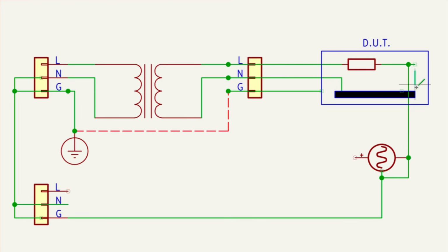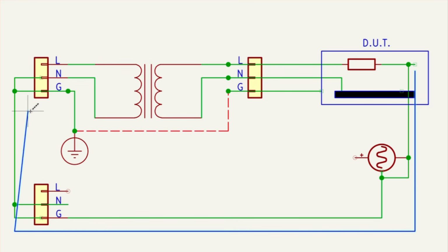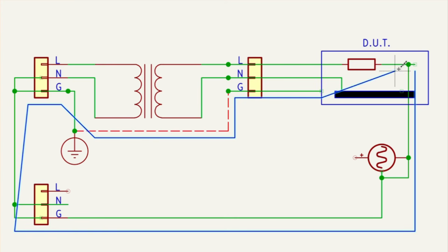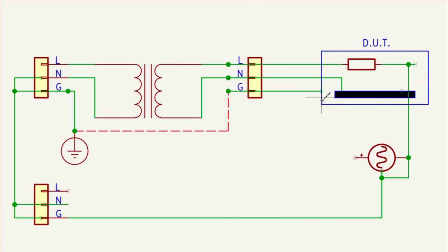Since this is floating, nothing blows up. You can see the path of the ground goes all the way here, comes over here, goes through, comes here, goes through ground, and stops here. At this point, the neutral is not shorted to the live wire, so there's no short, no problem. There's no closed loop, so there's no surge of current through the oscilloscope probes and nothing is damaged.